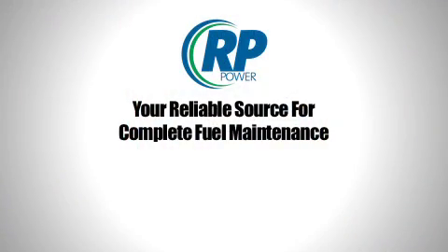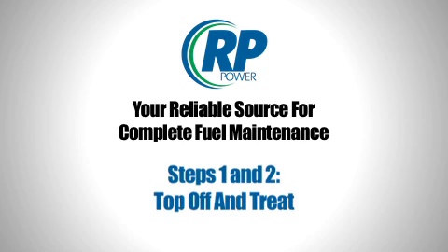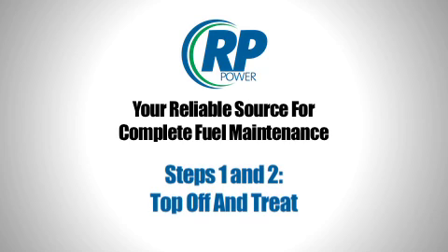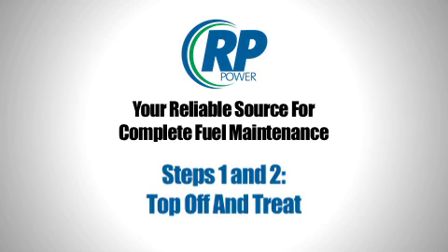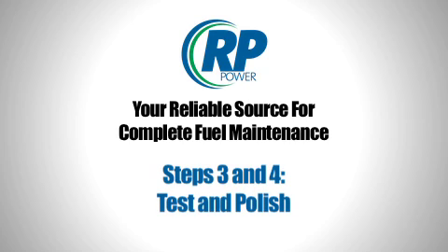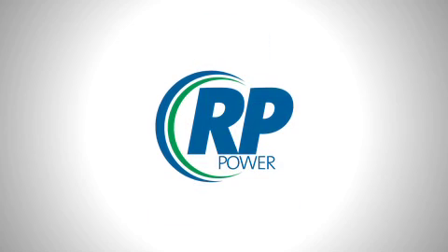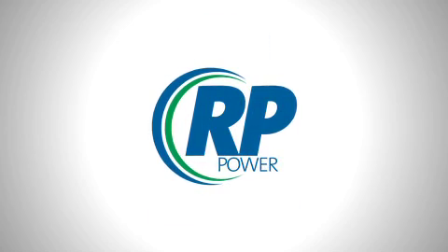So remember the RP Power Fuel Maintenance Program. A full tank is best. Use Steps 1 and 2, top-off and treatment, to prevent deterioration of your diesel and to maintain it in good condition. Use Steps 3 and 4 to check for fuel deterioration and correction should it be required. A standby power system cannot do its job without good fuel maintenance.